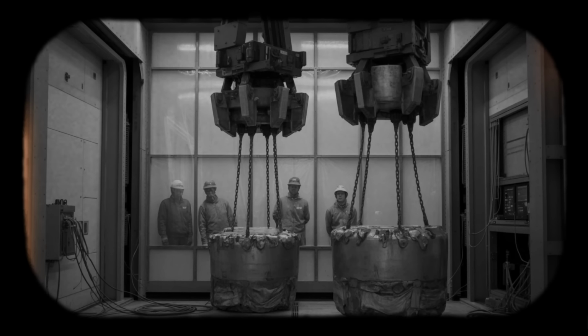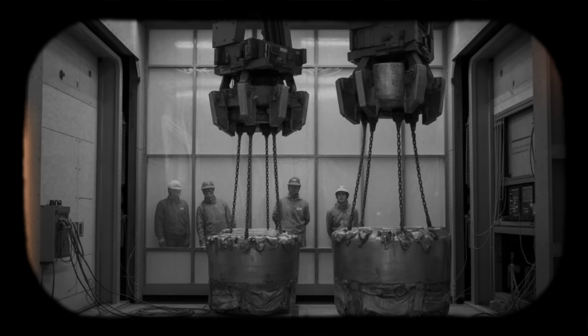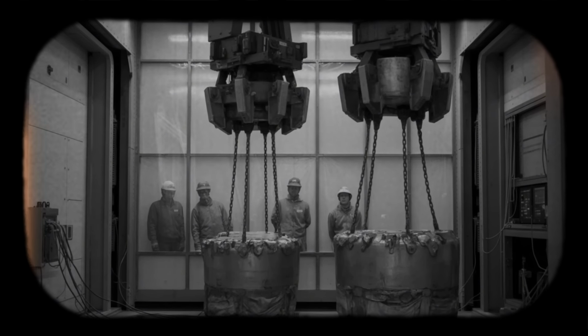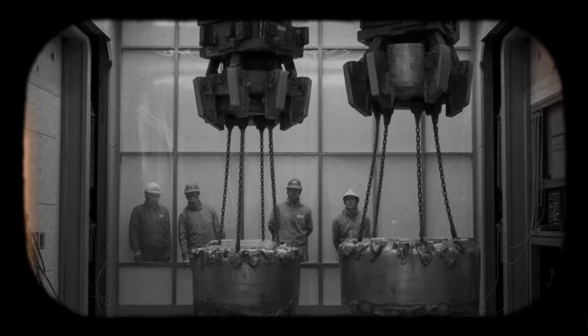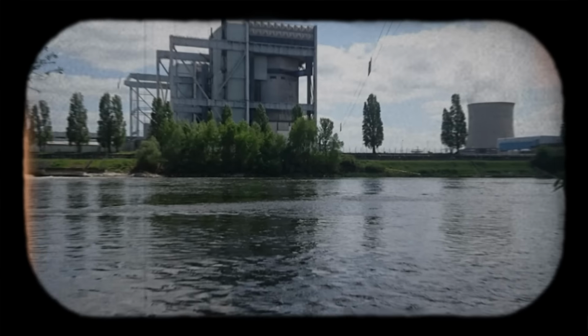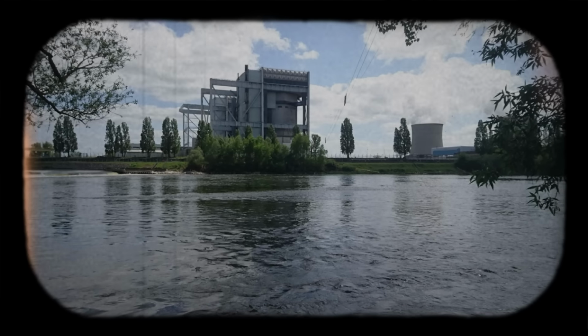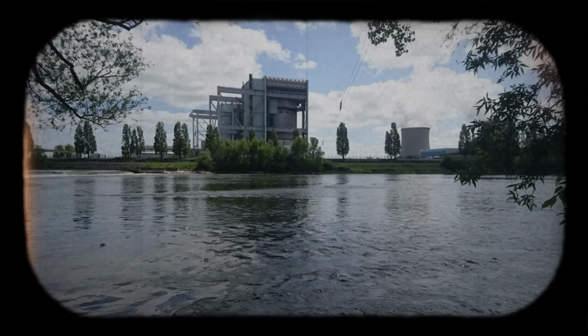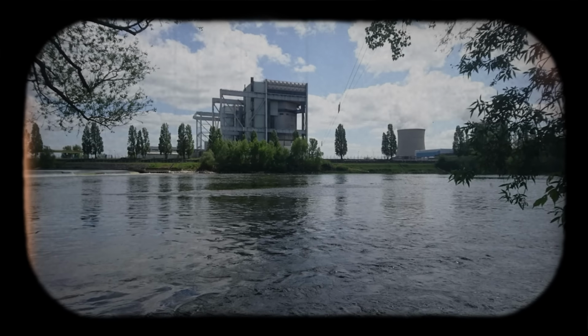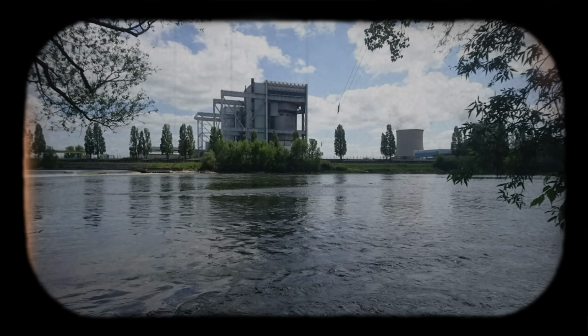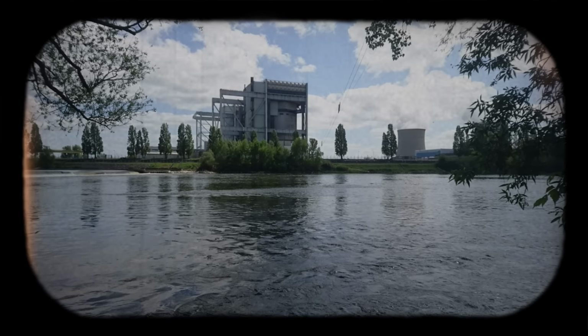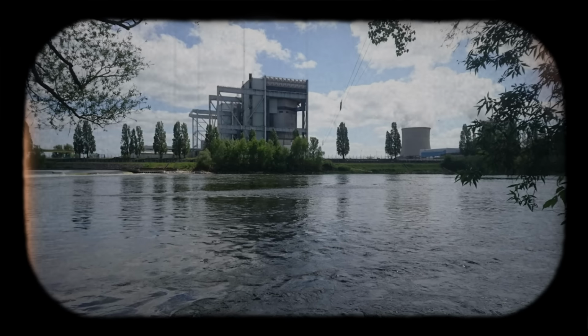Above the reactor vessel of Saint-Laurent-des-Eaux, a charging machine travels on rails across the top biological shield. Weighing several tons, the device positions itself over vertical standpipes that access individual fuel channels. A computer program controls displacement, alignment, and component transfer. The machine maintains carbon dioxide containment during operations, sealing to each standpipe before opening the channel and withdrawing or inserting fuel elements, graphite sleeves, or flow control devices.